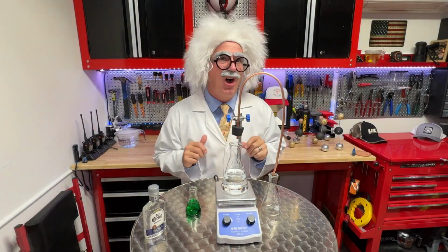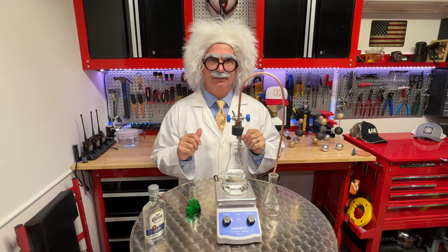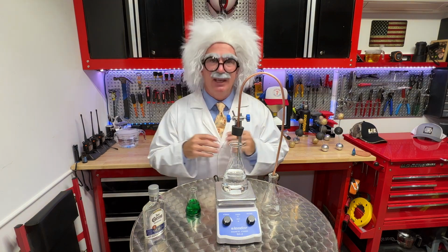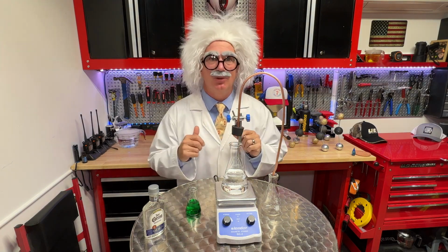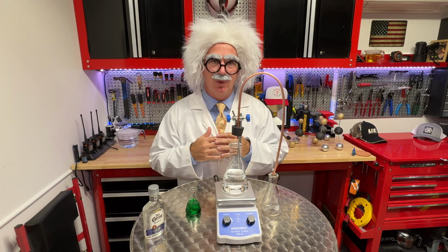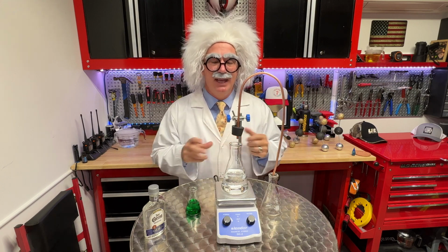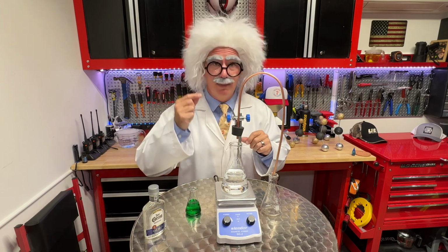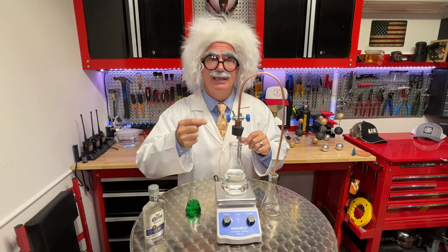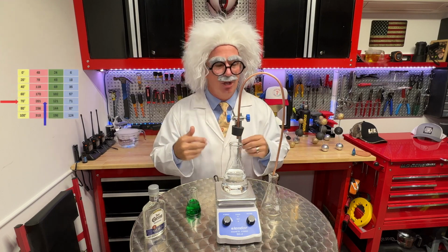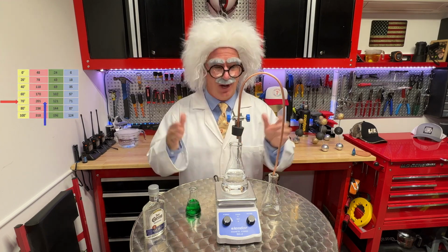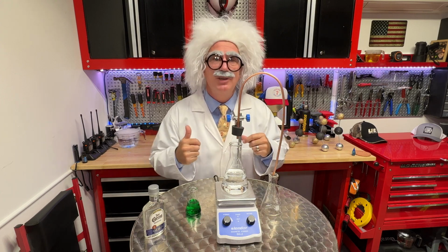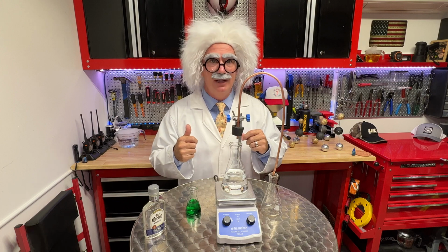Okay. So let's talk a little bit about glide. Not everyone understands what glide is. It's actually pretty simple. If we take two different chemicals that have different boiling points and we mix them together, either they are going to really like each other and they're going to have a new boiling point that is very consistent with whatever pressure it's at, or the two different chemicals are going to boil off separately. And that's what we find in the 400 series refrigerants. The 500, they like each other.